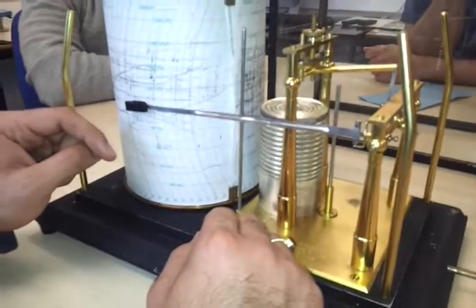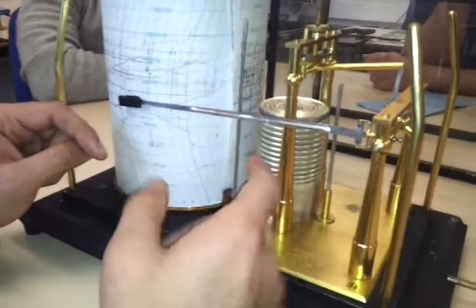This will be known as your pen arm. This will be known as the fiber nib. These will be the mechanical links and levers. It will be driving your aneroid capsules. This is your index error adjustment screw. There should be a transit plug over here.